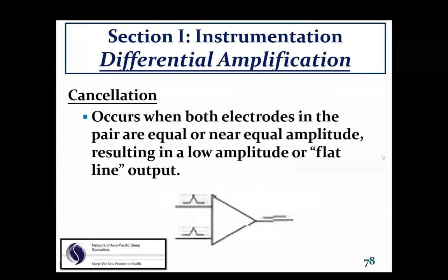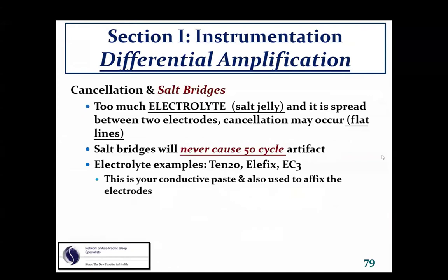Cancellation occurs, of course, we talked about this already. Cancellation occurs when both electrodes in the pair are equal or near equal amplitude, resulting in a low amplitude or flat line. Cancellation is a word they apply also to salt bridges. And now they're more commonly using the term electrolyte. Too much electrolyte, like salt jelly, which they don't really use anymore, is spread between two electrodes, you'll get a flat line. Salt bridges will never cause 50 cycle artifact. So electrolyte are products like Ten20, Elefix, EC3. This is your conductive paste and also used to affix the electrodes.